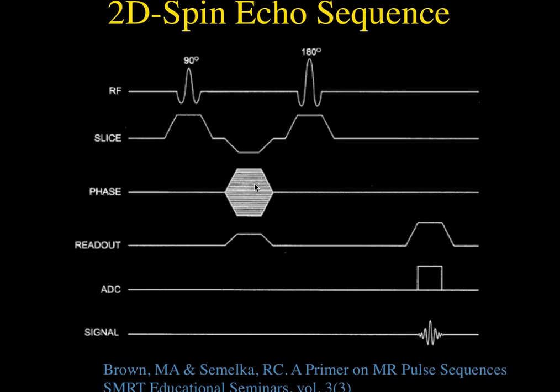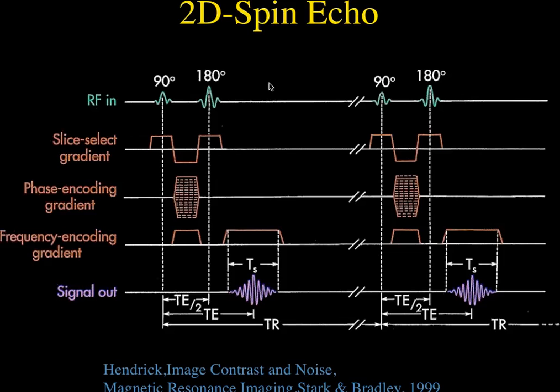This is the typical 2D spin echo sequence: 90-degree pulse, gradient, 180-degree pulse, and then the readout. In the early days, you'd give a 90-degree pulse, 180-degree pulse, phase-encoding gradient, another 180-degree pulse, and get your echo, then wait a TR period. The echo might be around 30-35 milliseconds after the 90-degree pulse, and with a TR of typically 700 milliseconds, there's a lot of dead time when nothing is happening — waiting for the z-component of the bulk magnetization to grow back up.